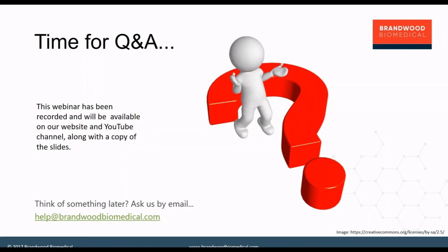As I presented before, the information that's included in the technical file relates to the verification, how the product meets the regulatory requirements, and all of the current DMR information, such as what's required for you to manufacture or produce the product. So you just need to include the information that demonstrates that the device meets the essential principles, and that should form the content of your technical file. So rarely would you need to go to the stage of including the design input documents.